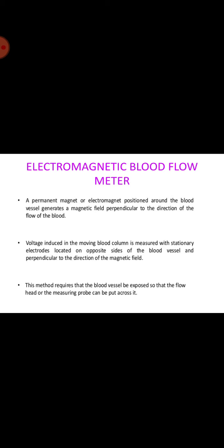For proper operation, the orifice of the probe must fit tightly around the vessel. For this reason, probes of this type are manufactured in sets with diameters increasing in steps of 0.5 or 1 mm from about 2 to 20 mm. The probes can be implanted for chronic use. In contrast, a long handle for use during surgery can also be used.